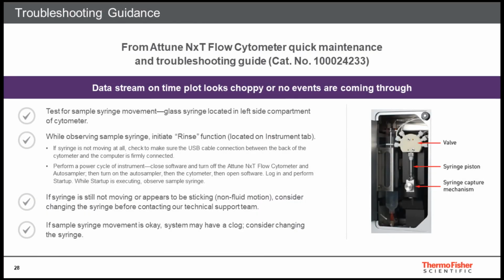Now let's discuss some troubleshooting tips and tricks to help identify problems with the Attune NxT and find expedient solutions. Let's take the scenario where the data stream via the time parameter looks choppy or no events are coming through. Test the sample syringe movement. Observe the smoothness of the plunger movement as it moves during sample acquisition or the rinse script. Erratic movements of the syringe will translate to non-uniform or choppy collection of data, and in this case, it's best to change the syringe. If the syringe is not moving at all or no errors are seen in the software, please check the USB connection. Make sure the USB is connected properly. Power cycle the Attune NxT. If a clog is suspected, run the unclog script.